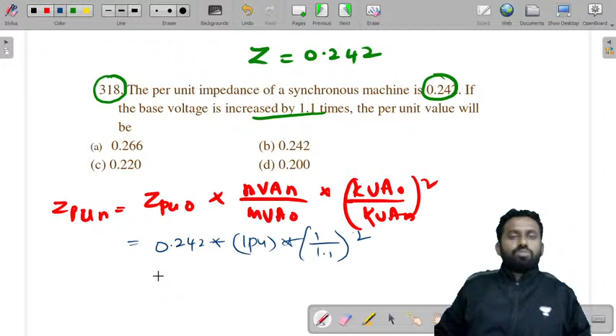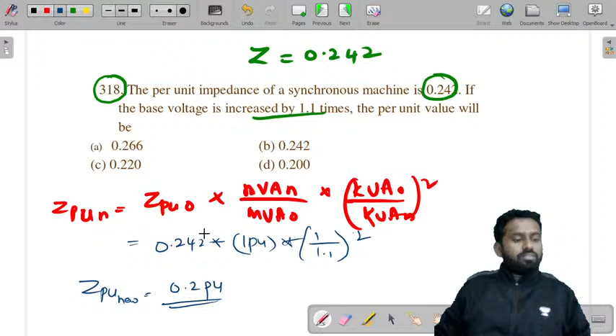Now what do you get? Z is 0.242 into the two MVAs, which is 1 per unit, and the KV increased by 1.1 times, so this is whole square. So Z per unit new, you'll get 0.2 per unit.